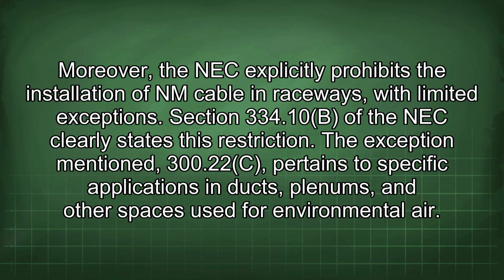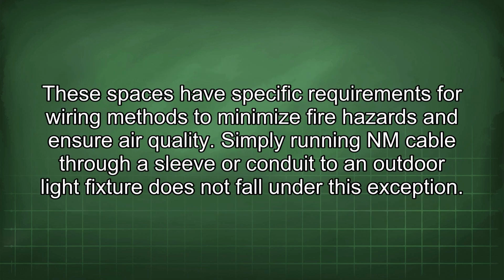Moreover, the NEC explicitly prohibits the installation of NM cable in raceways, with limited exceptions. Section 334.10(B) of the NEC clearly states this restriction. The exception mentioned, 300.22(C), pertains to specific applications in ducts, plenums, and other spaces used for environmental air. These spaces have specific requirements for wiring methods to minimize fire hazards and ensure air quality.